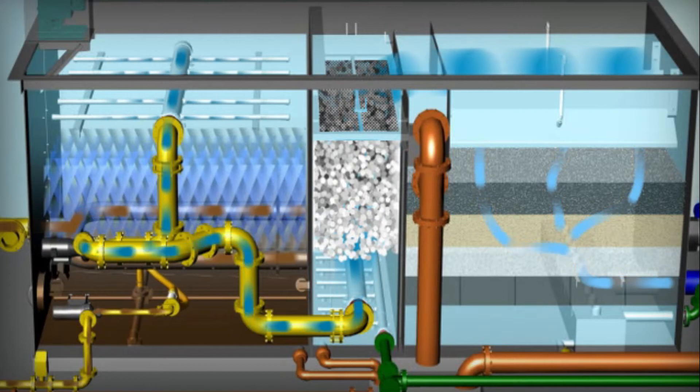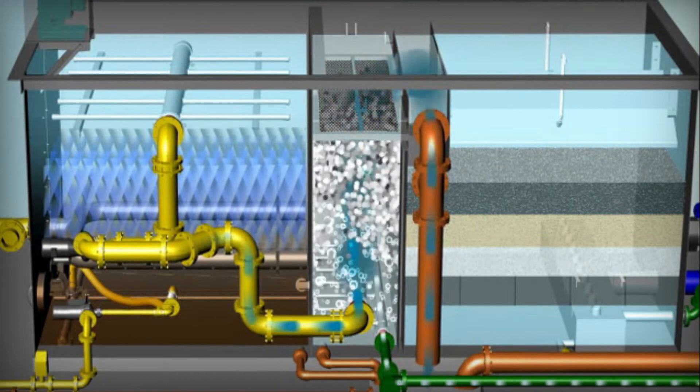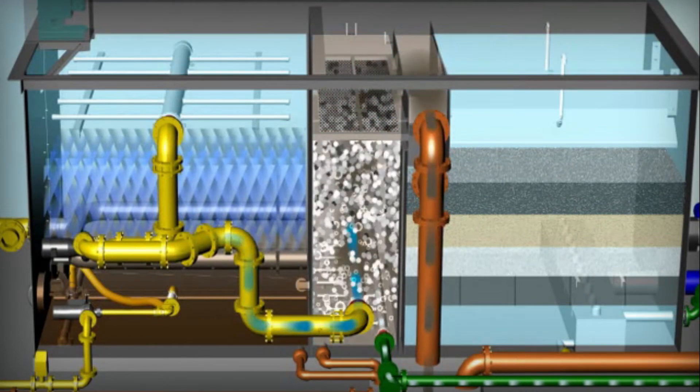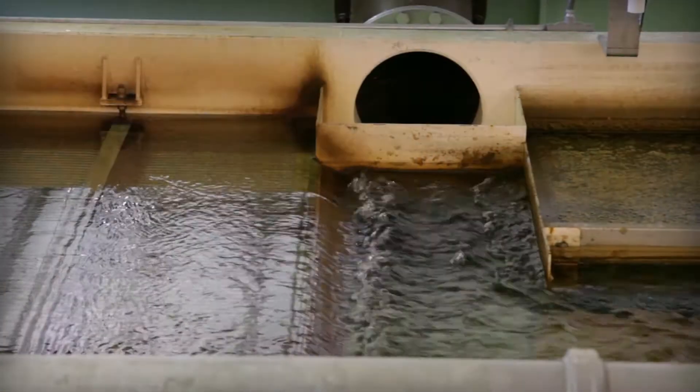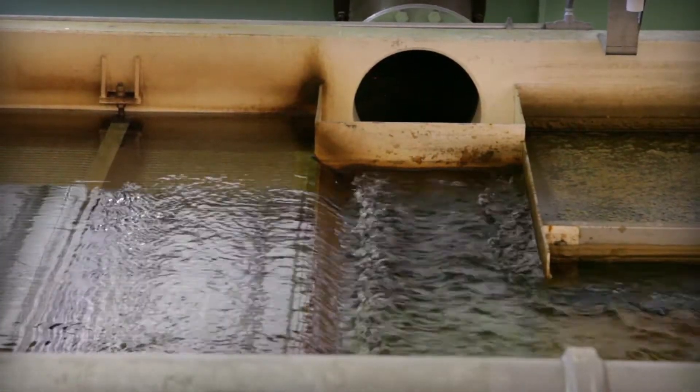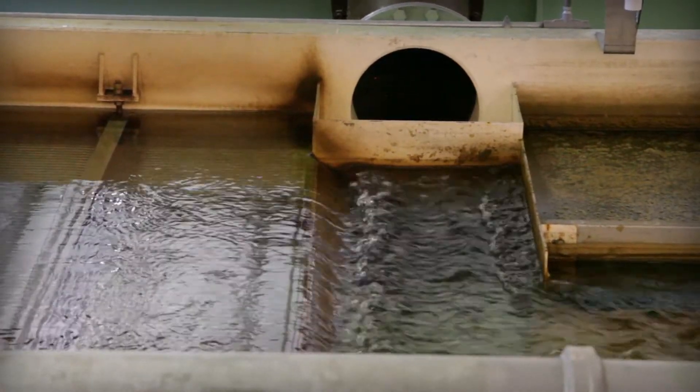When sufficient head loss is built up in the adsorption clarifier, a flush cycle is automatically initiated. During a flush cycle, clarified water flow continues while air is introduced, expanding the bed and providing high energy to release the bound solids.